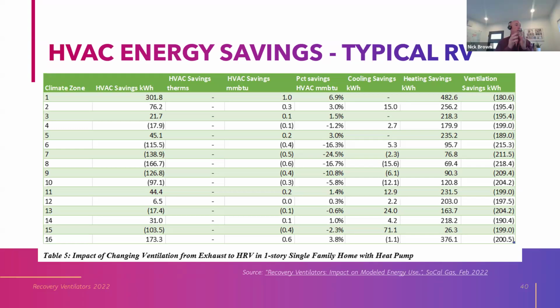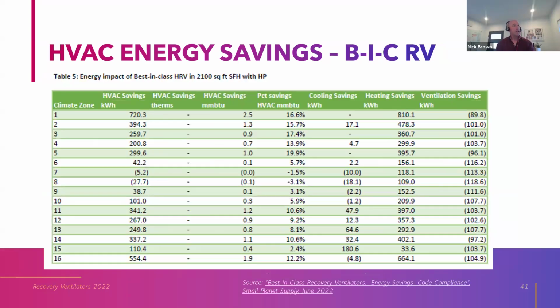And you can see in climate zones 1 and 16, the greatest savings, right? Those are the most heating dominated climate zones in the state. Whereas 6 through 9, 10, 15, all show big negatives. You're actually using more energy than you would with exhaust only ventilation. Make sense? Now let me show you a best-in-class HRV in the same type home.